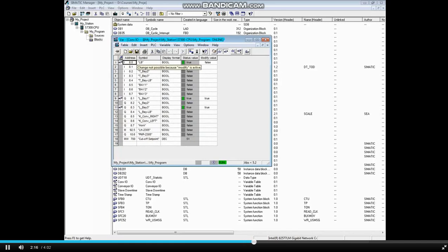The lightning bolt mark appears next to each modified I/O point. Notice that the two outputs have been changed from false to true. Even though both outputs are being written to from the code, they are being overwritten by this permanent modify. The input, however, did not change to false. This is because the modify is being sent out at the bottom of the scan, but the inputs are read in at the top of the scan. Click the modify button again to stop the permanent modify.